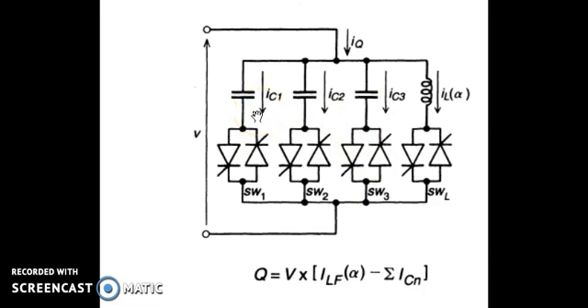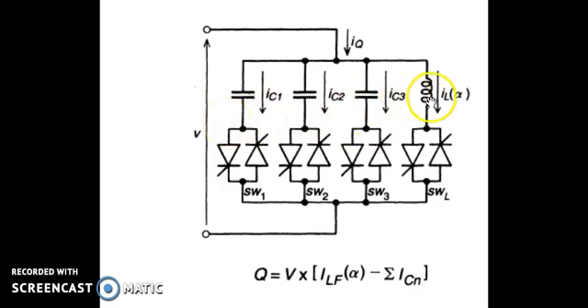The three capacitor components shown are thyristor switched capacitors — not thyristor controlled capacitors — and their firing angle is constant. The reactive component is a thyristor controlled reactor. The total reactive current applied by this combination is the current through the inductor minus the sum of the currents through the switched-on capacitors. For example, if C2 and C1 are off, the net current will be IL minus IC3, and multiplying by the net system voltage gives the reactive power output.